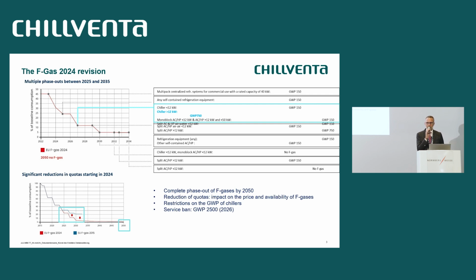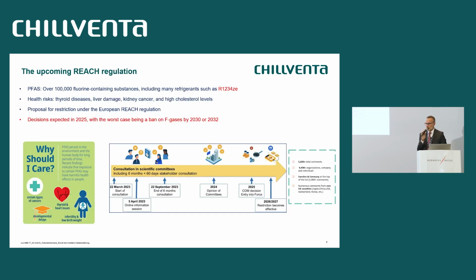And then, talking about chillers, there will be specific bans. In terms of GWP, from 2027 there will be a 750 GWP limit. And last but not least, a service ban from 2026 for all refrigerants above 2,500. All these facts contribute to the movement of the market towards natural refrigerants. It's not only the F-gas, it's also the REACH regulation.